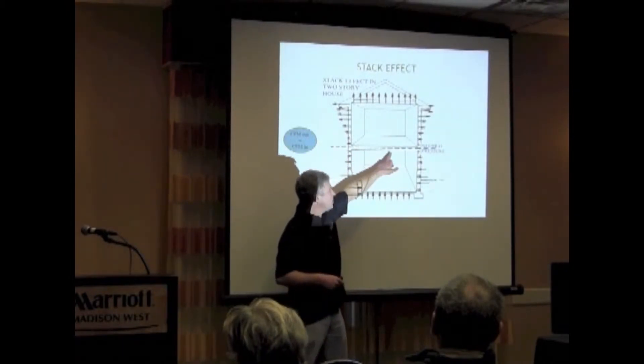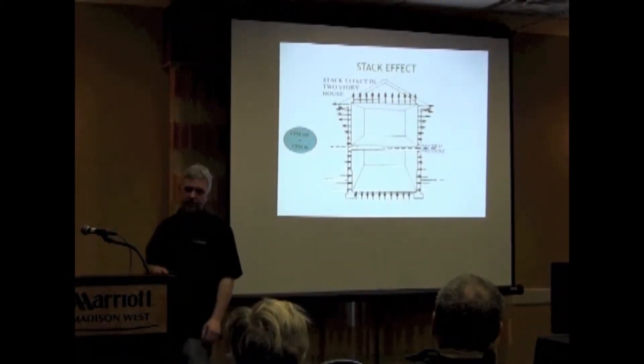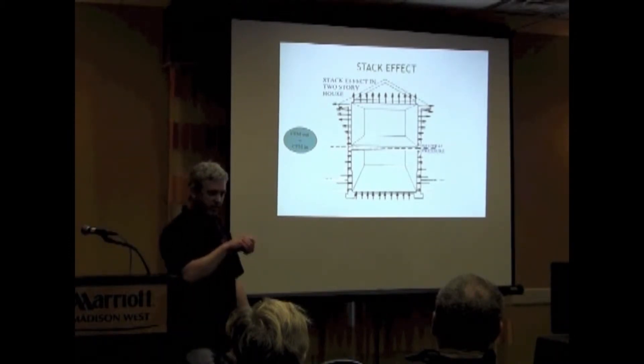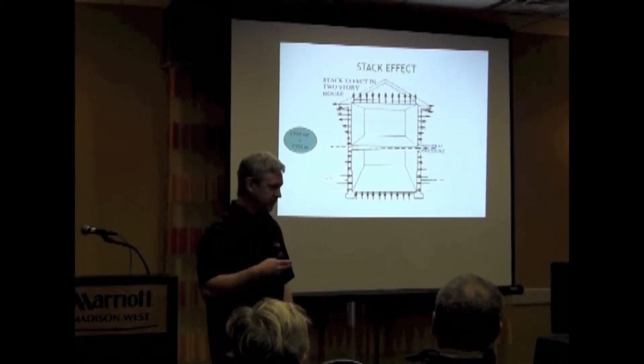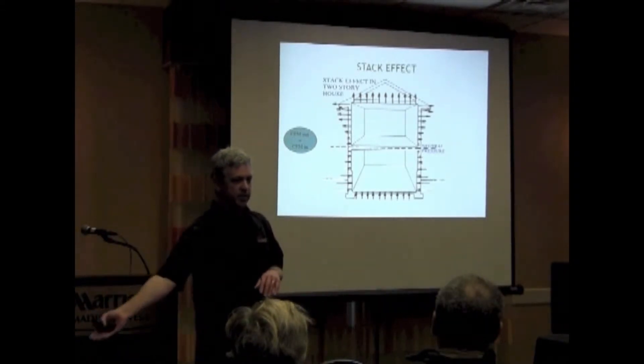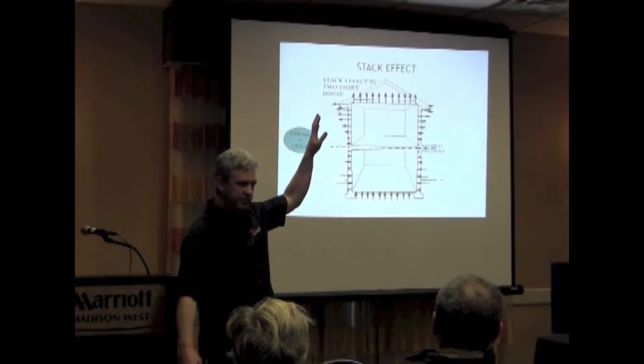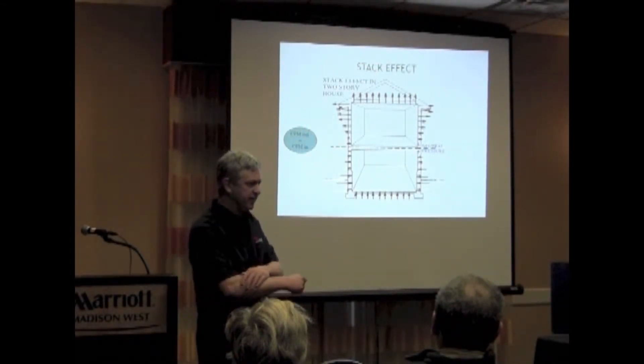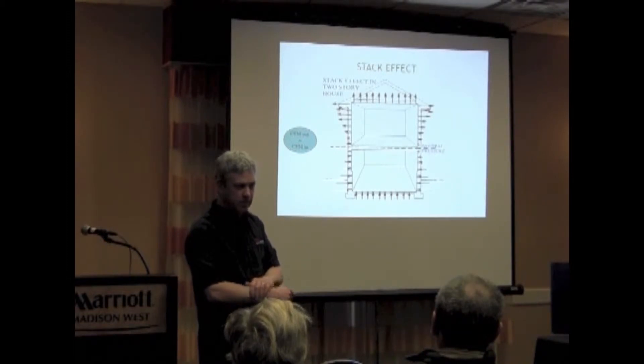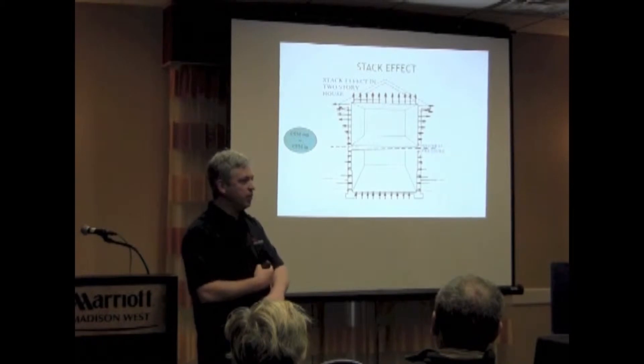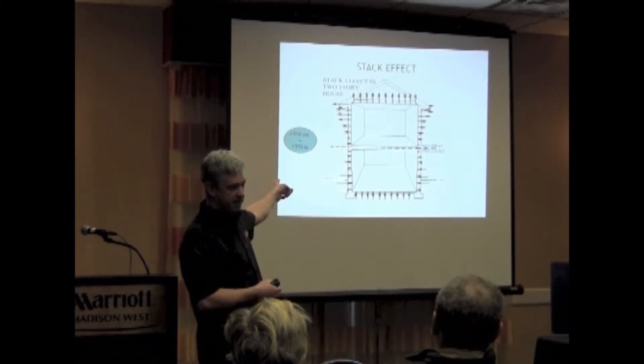This neutral pressure plane is not always at the floor. On especially a two-story home, air will come in on the first floor windows and leave on the second floor. So if you sit by your first floor window, you always feel a draft. But if you go up and sit on the second floor with the exact same age and style of windows, you won't feel that draft — because of stack effect.